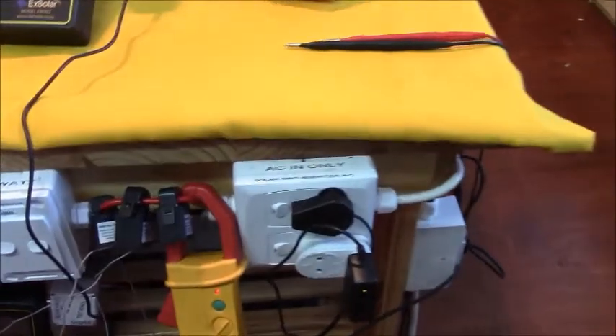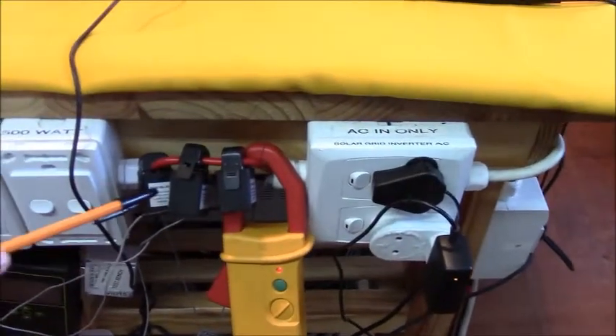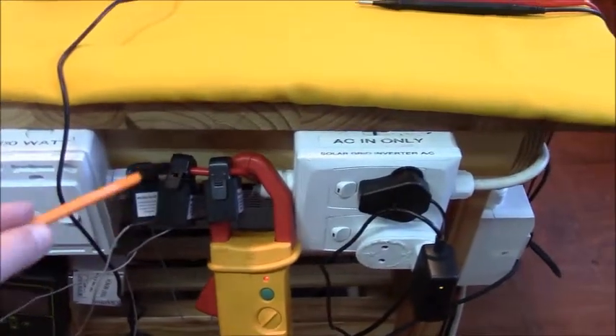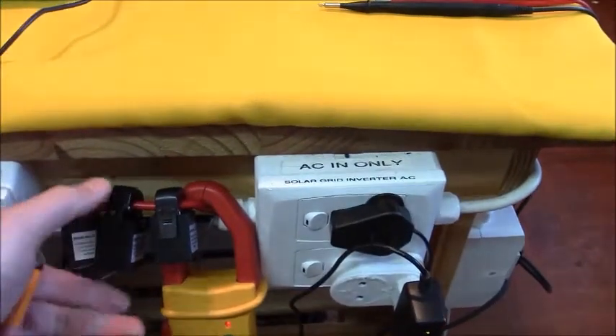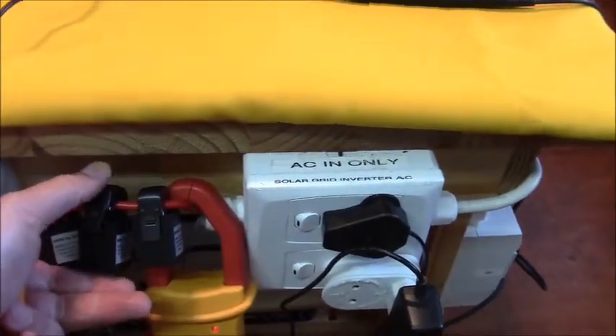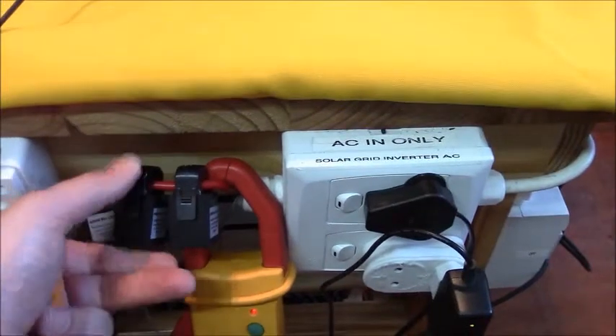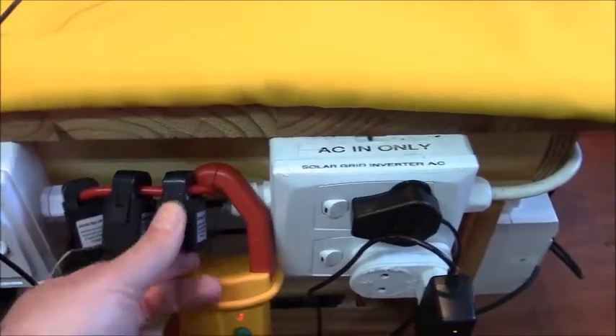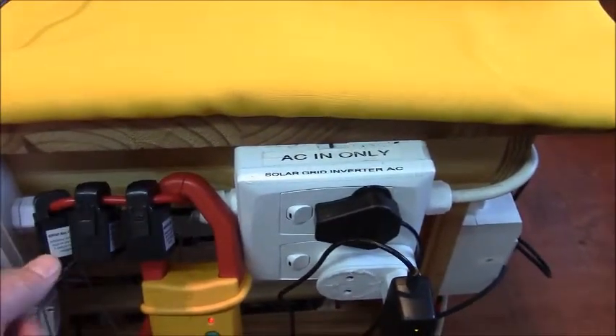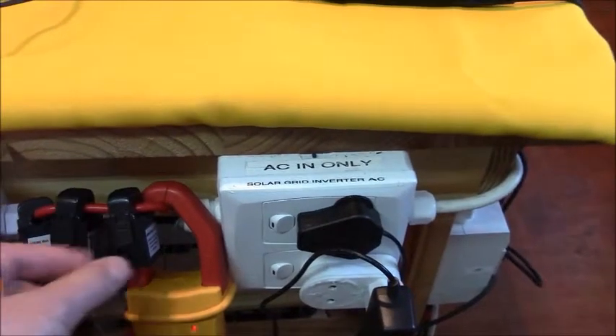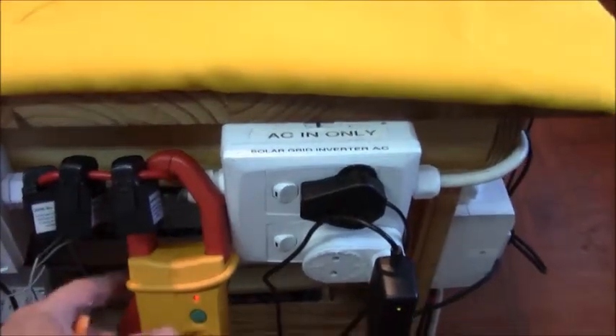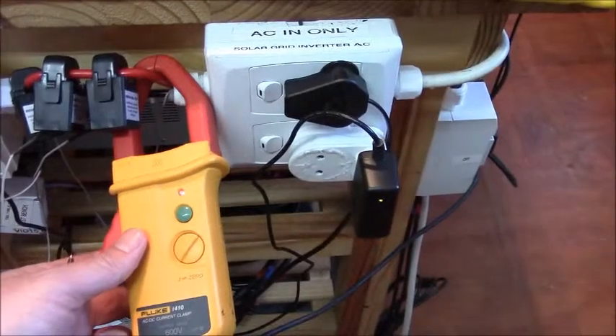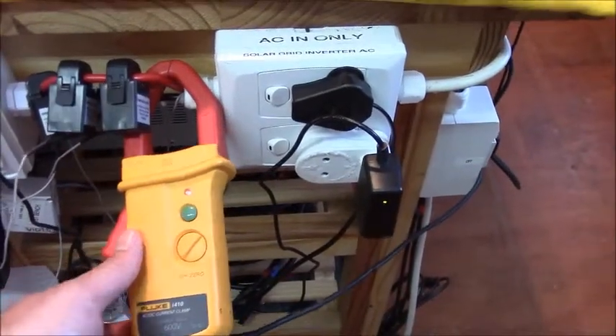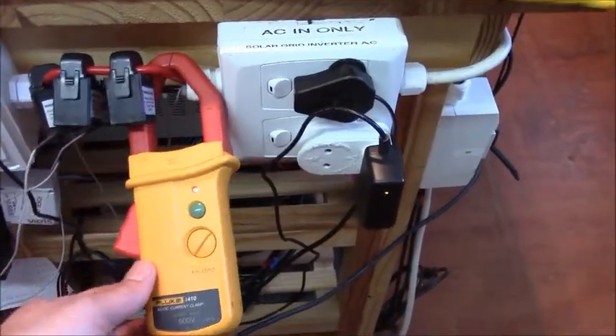Here we have the AC sensors. We've got 3 sensors on the same piece of wire. If you notice, one of these sensors is not actually clipped closed. All the sensors must be closed. So we've got sensor number 1, sensor number 2 and sensor number 3. And this is the AC sensor for the Fluke.